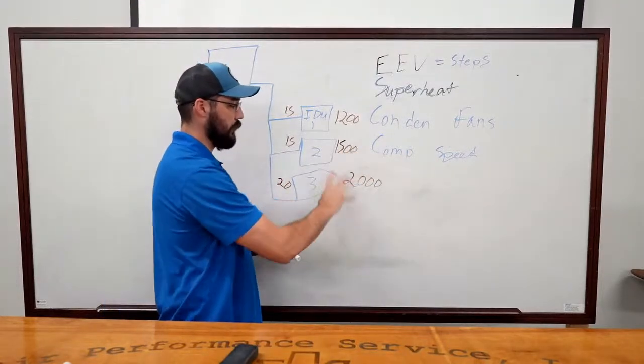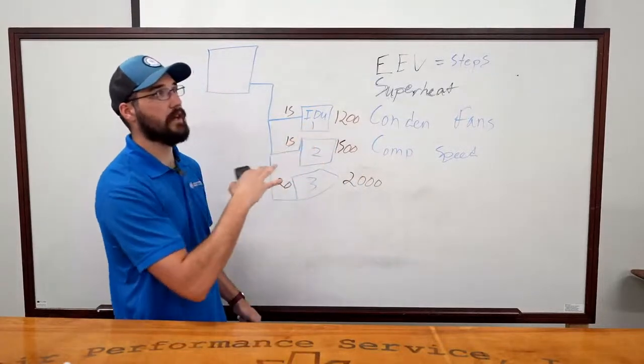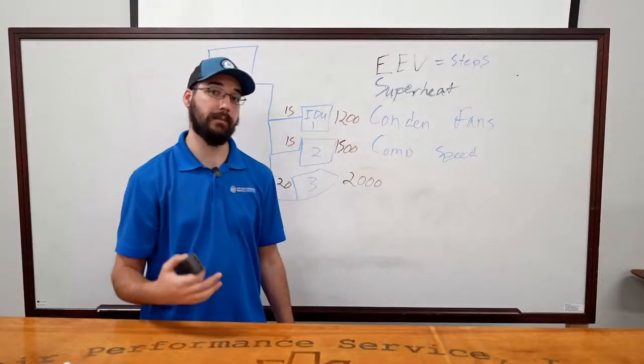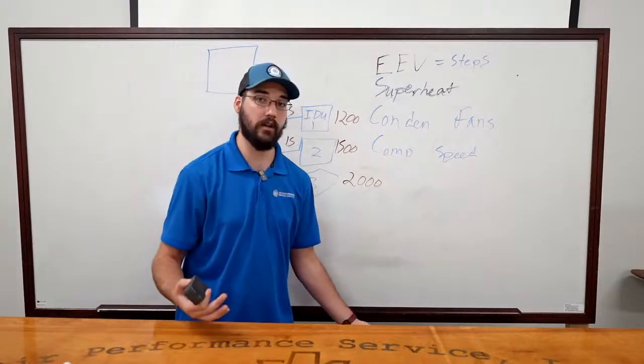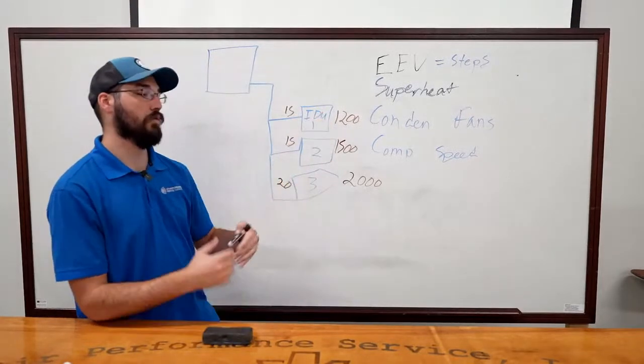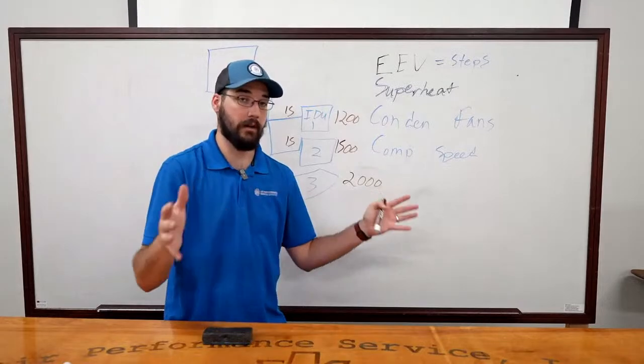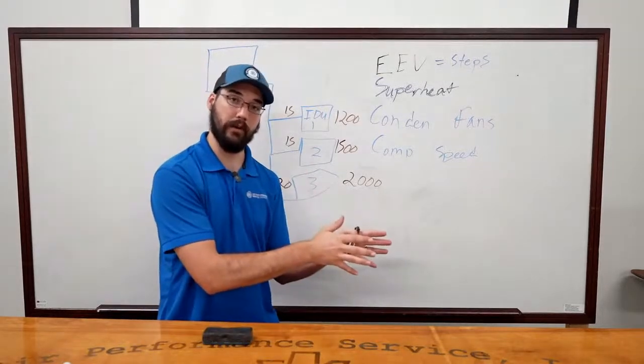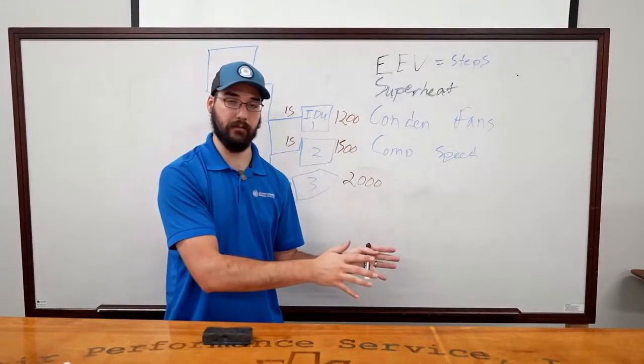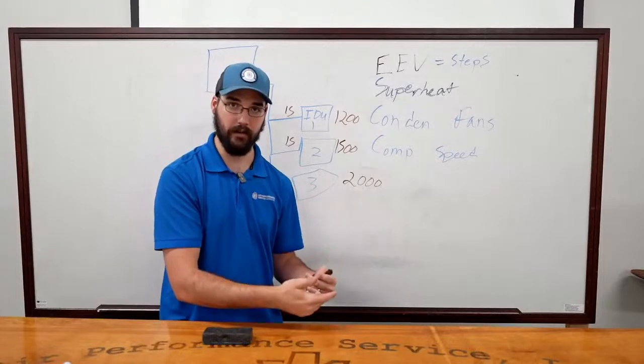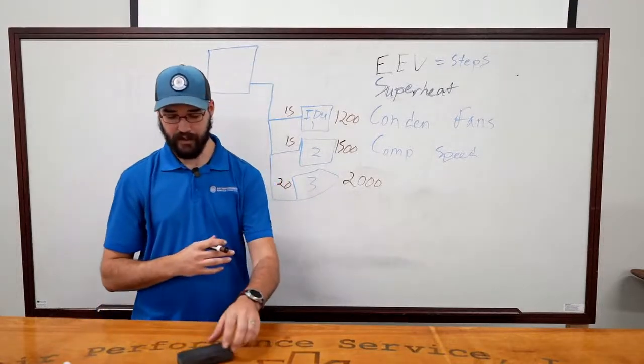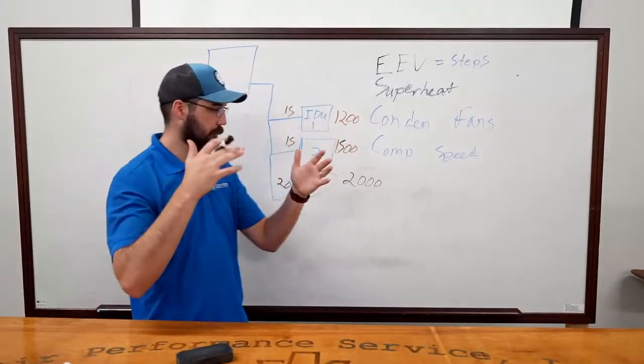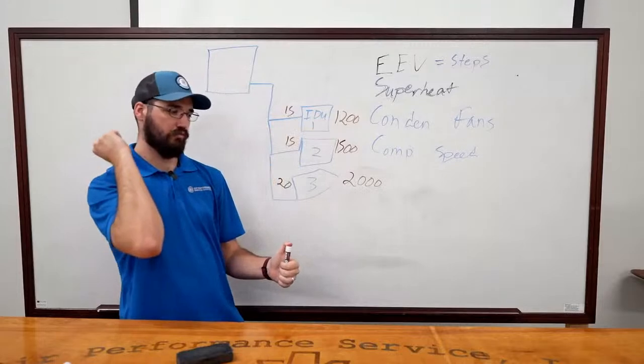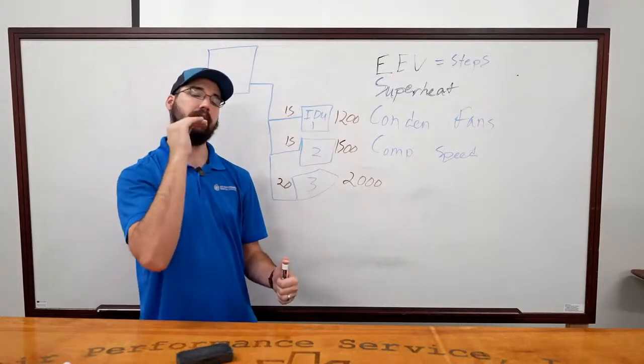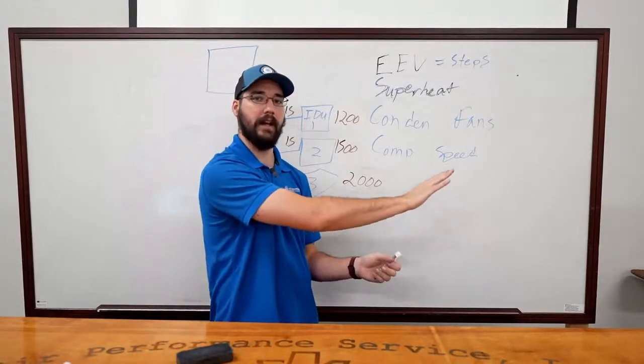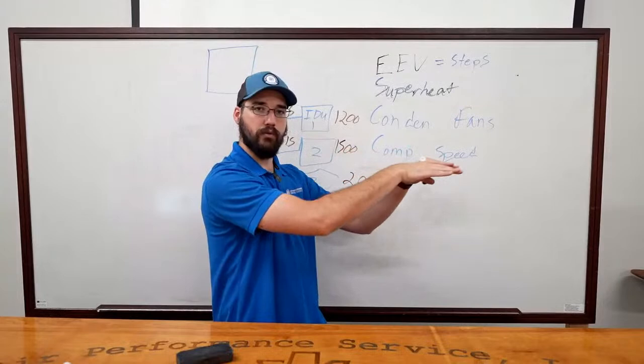So what these would normally be is, usually I rarely see them get above 1,000 steps, if even that high. 500 is not uncommon to see on these indoor units when the load is under control. So when we're not talking about an excessive load or a pull down, when we're at set point and we have a good charge in the system, those valves don't have to open that much to maintain. Because that's the other thing you have to understand: it's a different concept, as I mentioned in the beginning. We're not trying to just fly to set point and satisfy it. No, these systems are designed to, like a plane landing, ease into set point and cruise right there at it.